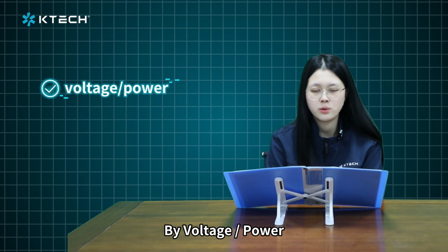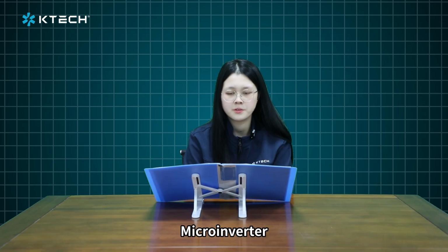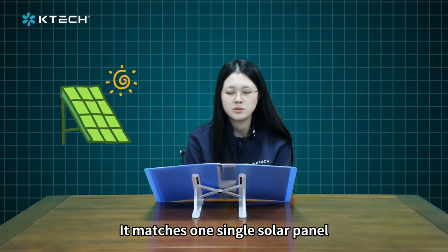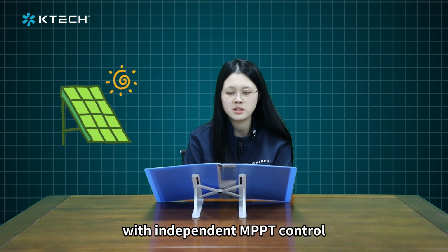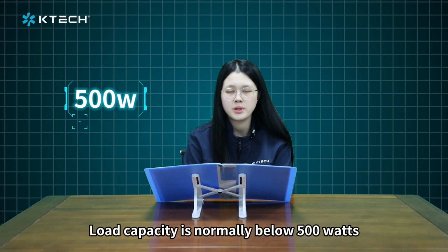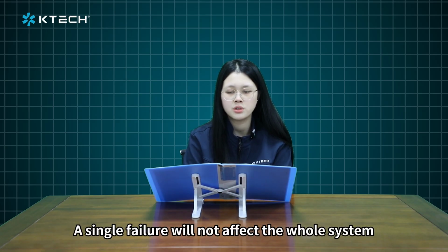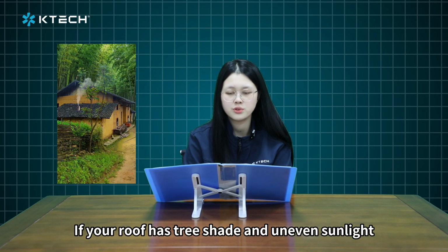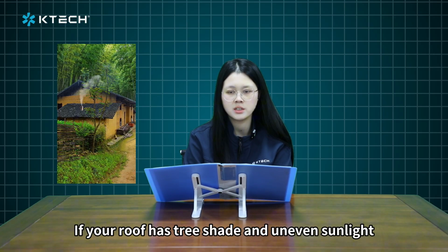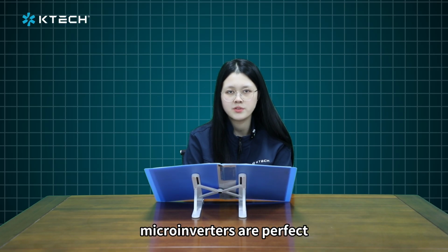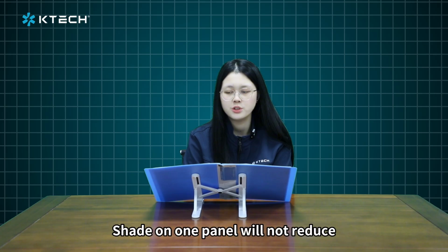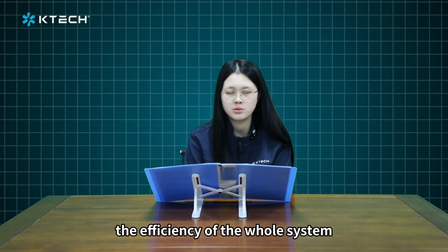By voltage and power, microinverter. It matches one single solar panel with independent MPPT control. Load capacity is normally below 500 watts. A single failure will not affect the whole system. If your roof has tree shade and uneven sunlight, microinverters are perfect. Shade on one panel will not reduce the efficiency of the whole system.